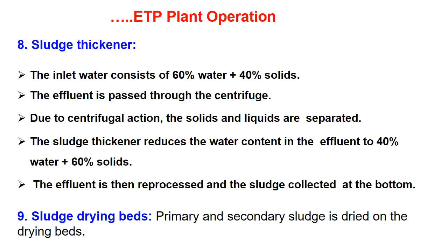Number eight is the sludge thickener. The inlet water consists of 60% water and 40% solids. The effluent is passed through the centrifuge — due to centrifugal action, solids and liquids are separated. The sludge thickener reduces the water content to 40% water and 60% solids. The effluent is then reprocessed and the sludge collected at the bottom. Finally, the primary and secondary sludge is dried on the sludge drying bed and taken away for further use.